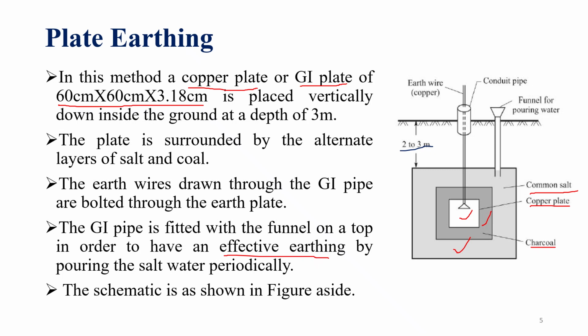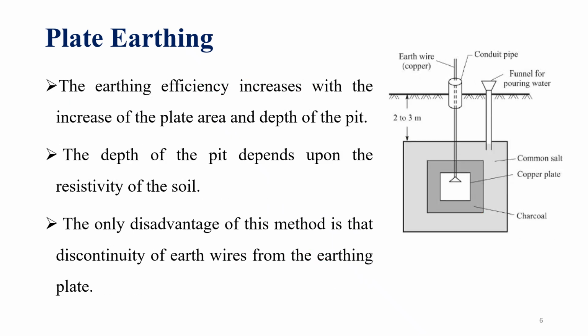So this is the arrangement of plate earthing, and the earthing efficiency is going to increase with the increase of plate area and depth of the pit. Under basic design we are going to use 2 to 3 meters depth only, but based upon the requirement and the amount of current that we have to earth, you can go to more depth also. And with the increase in plate area, 60 by 60 by 3.18 as previously discussed, if you further increase the area of that plate, then the effectiveness of the earthing is going to increase.